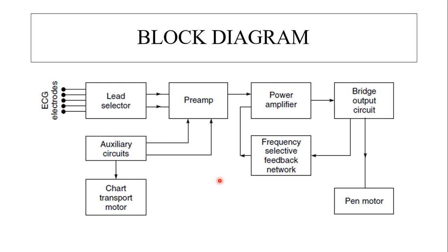The base of one input transistor of this amplifier is driven by the preamplified unsymmetrical signal, and the base of the other transistor is driven by the feedback signal resulting from the pen position, connected through a frequency selective network.